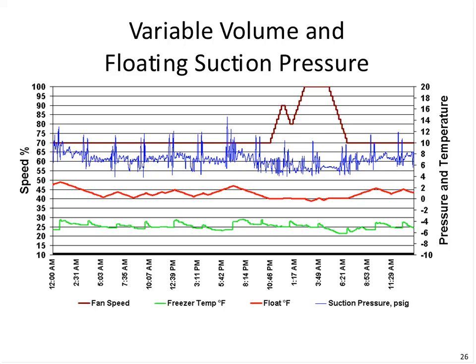But then notice after the temperature returns back to its really below its set point, we slow the fan down, and then we start floating the suction pressure. So throughout the day, you can see we're getting an average of 1 or 2 degrees of float, and that could be 2 to 4% energy savings. And we're getting, of course, fairly continuous energy savings on the fan. So there's an example of floating head pressure and floating suction pressure.